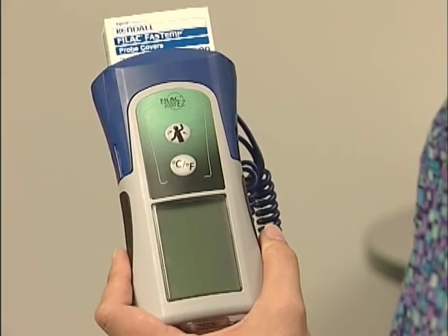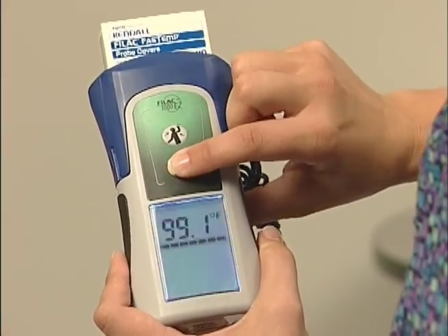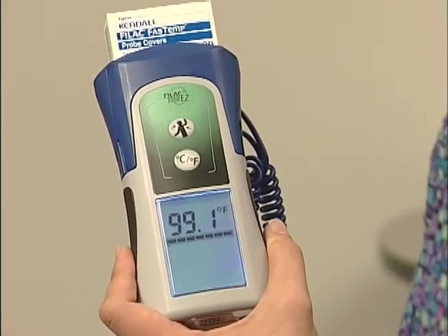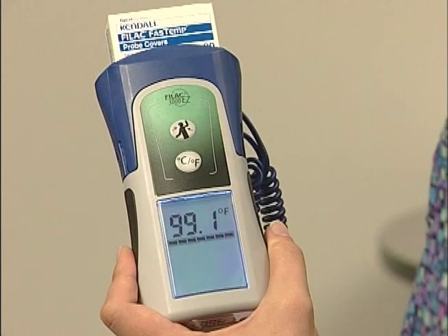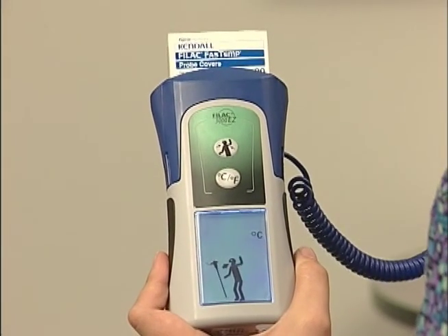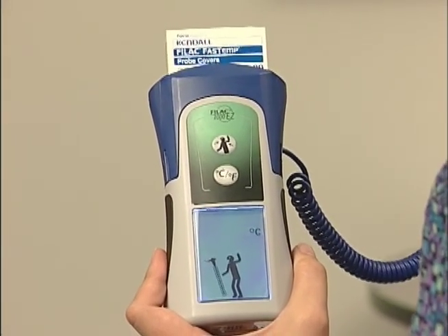You may view the most recent temperature reading by simply pressing the C degrees, F degrees button on the front panel. The probe must be in the chamber and not have been removed since the last temperature was taken to display the reading. Withdrawing the probe from the chamber will erase the last temperature taken from memory.